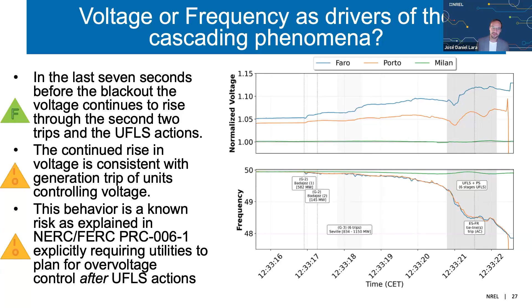Now, the question about inertia keeps popping up about this event. And I want to emphasize that I think the community has been looking for an event like this to talk about inertia because we've done so much research on it. However, if we go back in time in Spain, to January 9th of 2025, the same year, there was a huge generation trip during a high penetration of wind in Spain. The wind was providing about 70% of the load in Spain at about 2:30 in the morning, Central European Time, and a 1 gigawatt loss of generation happened with the loss of a nuclear power plant.